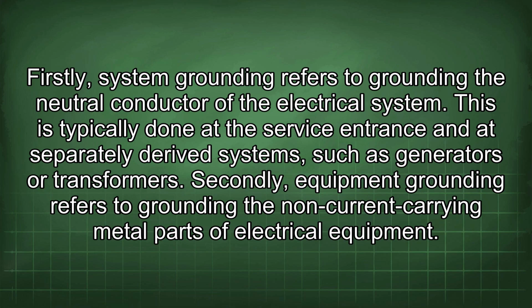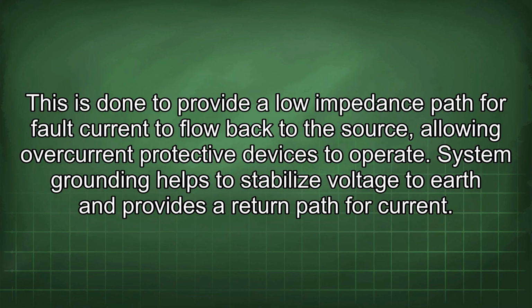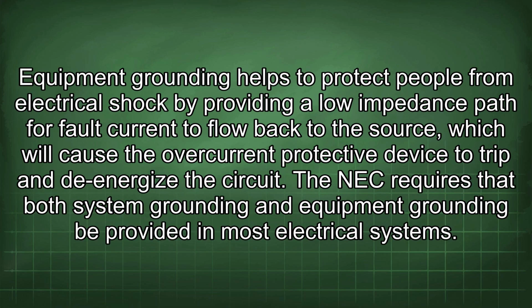Secondly, equipment grounding refers to grounding the non-current carrying metal parts of electrical equipment. This is done to provide a low impedance path for fault current to flow back to the source, allowing overcurrent protective devices to operate. System grounding helps to stabilize voltage to earth and provides a return path for current. Equipment grounding helps to protect people from electrical shock by providing a low impedance path for fault current to flow back to the source, which will cause the overcurrent protective device to trip and de-energize the circuit.